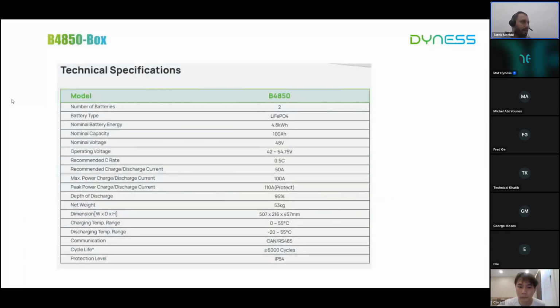Let's dive into some technical specifications of the B4850 box. As we said before, it includes 2 pieces of B4850, which means it's around 4.8 kilowatt hour. The recommended C rate is 0.5 C. It has a peak power charge and discharge current of around 110 ampere. As a special advantage of our products, the DOD, or depth of discharge, is 95%. As we said before, the protection level is also IP54.